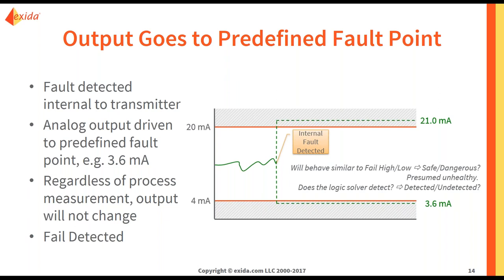In some cases, your output can go to a predefined fault point. If a fault is detected by the transmitter, the transmitter can then be programmed to drive the output to a predetermined value. We call this fail detected. However, whether it is classified as safe, dangerous, detected, or undetected depends on your application. The reason is because we don't know yet if your logic solver knows that your transmitter detected a failure. I will get into that more in a bit.